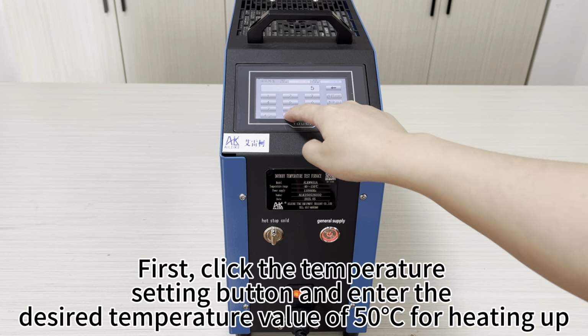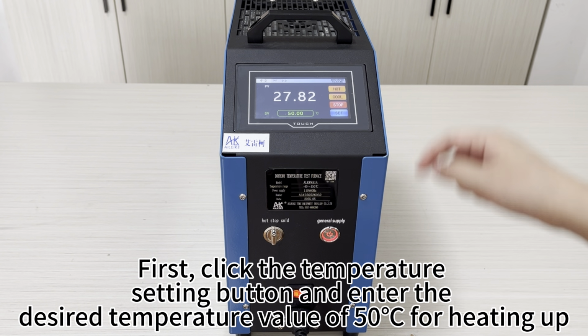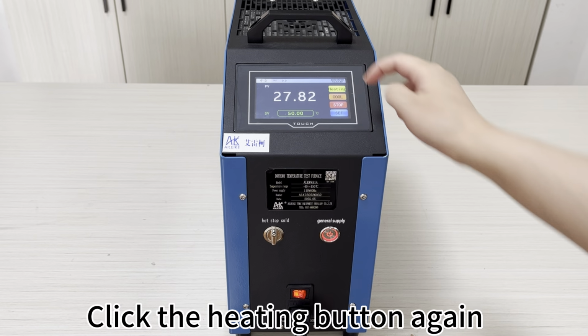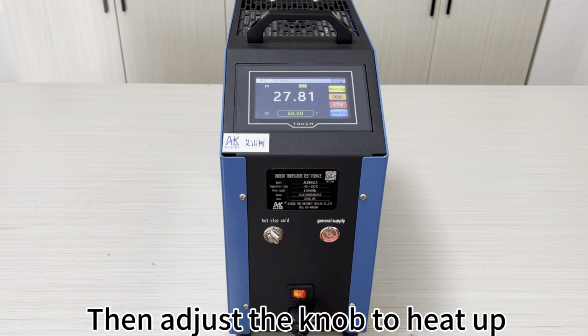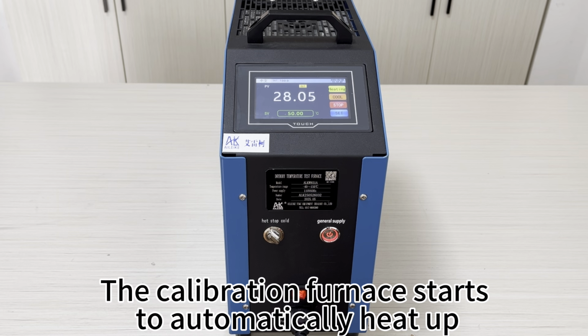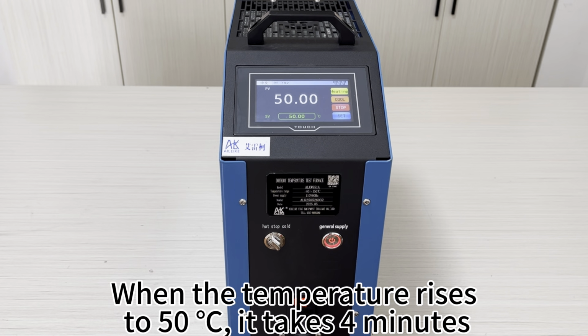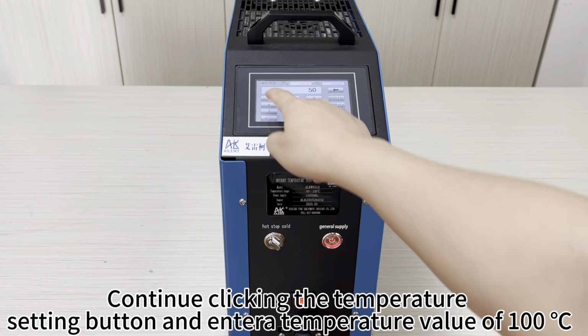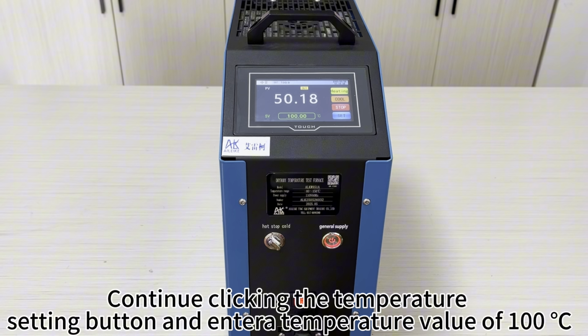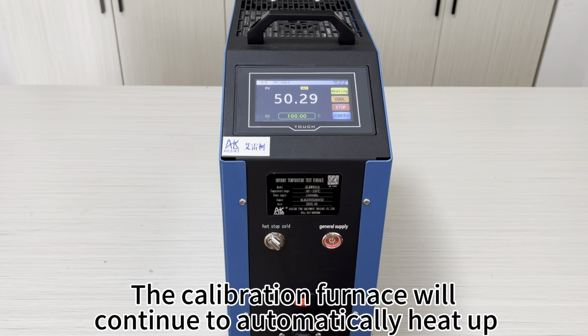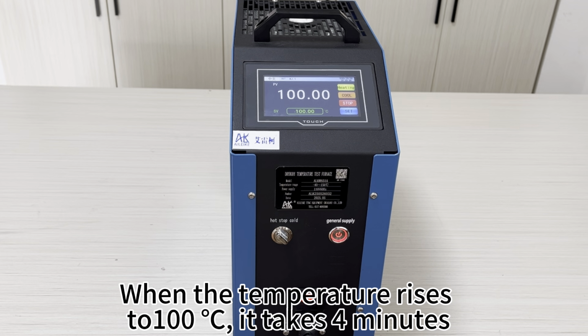First, click the temperature setting button and enter the desired temperature value of 50 degrees Celsius for heating up. Click the heating button again, then adjust the knob to heat up. The calibration furnace starts to automatically heat up. When the temperature rises to 50 degrees Celsius, it takes 4 minutes. Continue clicking the temperature setting button and enter a temperature value of 100 degrees Celsius. The calibration furnace will continue to automatically heat up. When the temperature rises to 100 degrees Celsius, it takes 4 minutes.